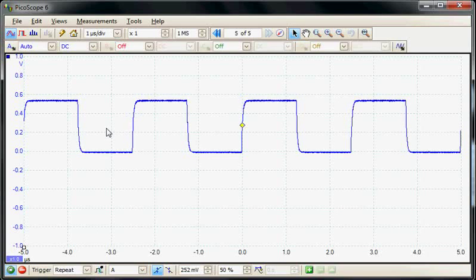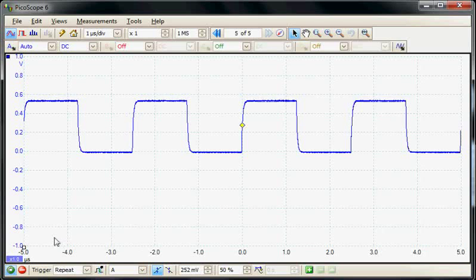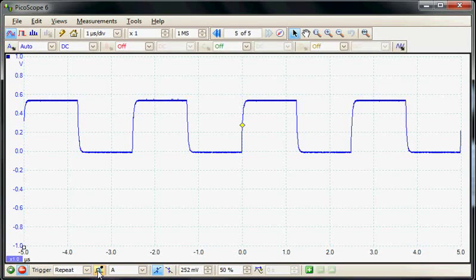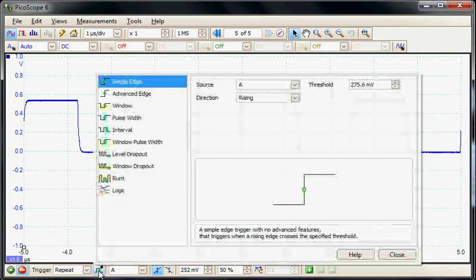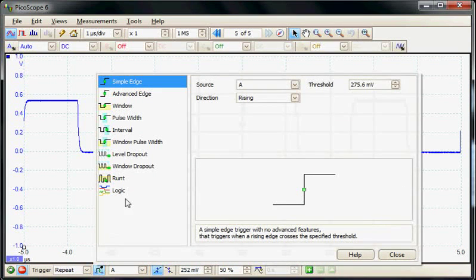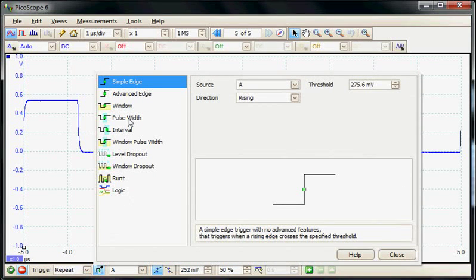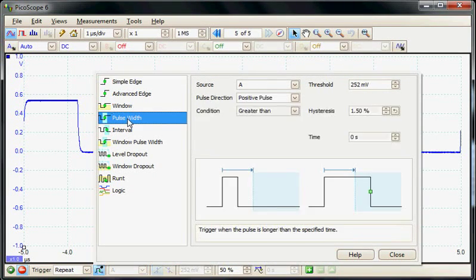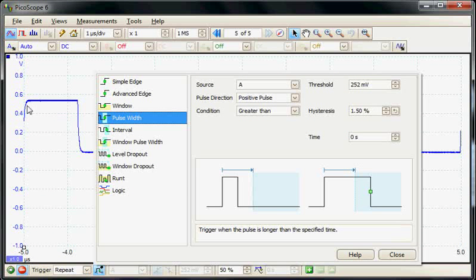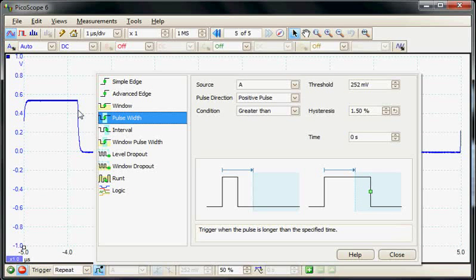The first thing we're going to do is define the advanced trigger. I'll stop the acquisition and select the advanced trigger library. The trigger I'm going to be using is Pulse Width Trigger, looking for a pulse which is wider than the normal width of this sequence.